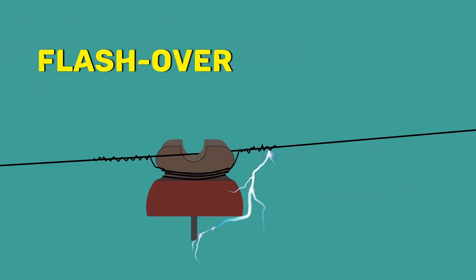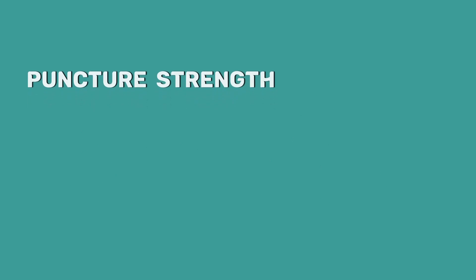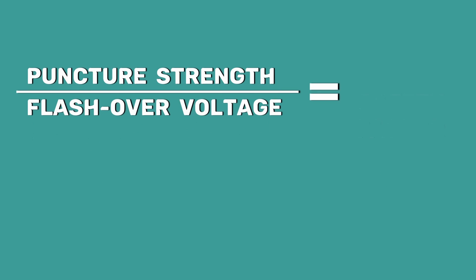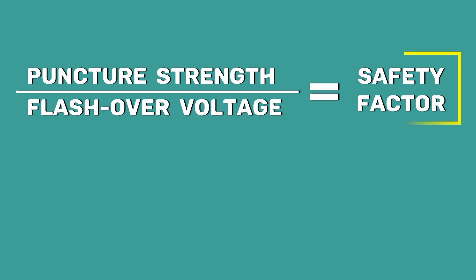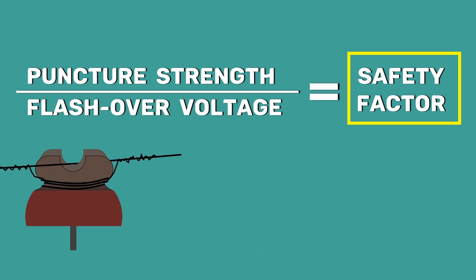Therefore, when the insulator breaks down by puncture, it is permanently damaged and cannot be used anymore — it must be replaced with a new one. But the insulator is not damaged by a flashover. To avoid a puncture, a sufficient thickness of porcelain is provided in the insulator. The ratio of puncture strength to the flashover voltage is known as the safety factor. The value of the safety factor should be high so that flashover takes place before the insulator gets punctured. For pin type insulators, the value of the safety factor is about 10.